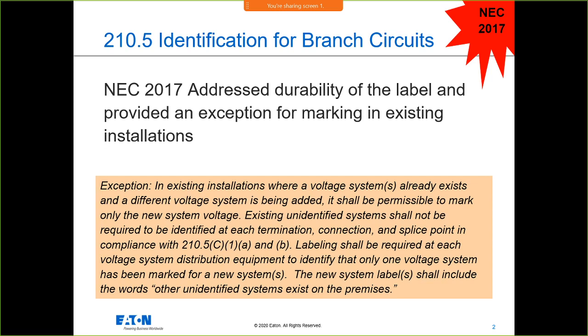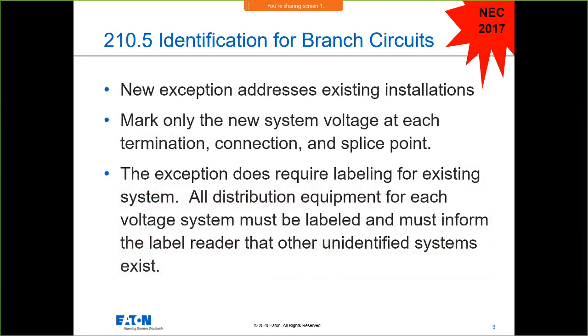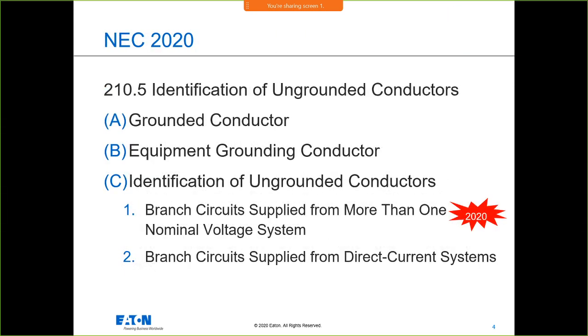Provide the identification. I think I'm almost positive we changed this in the 20 cycle, where in the 17 cycle we talked about the durability of the label, and they provided some new exceptions for existing installations. And there's always confusion: do you only have to mark the new system voltages at each termination? Do you have to go back and modify and mark everything in that facility the moment you start adding a new voltage into an installation? I think that was where we had some public inputs, and I know Don Ganier, I think you were instrumental in some of this stuff.